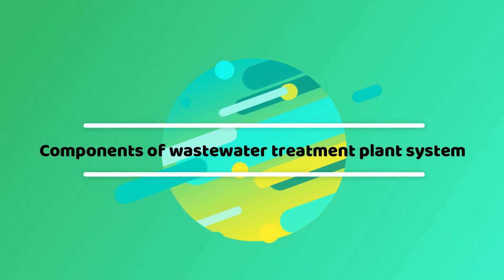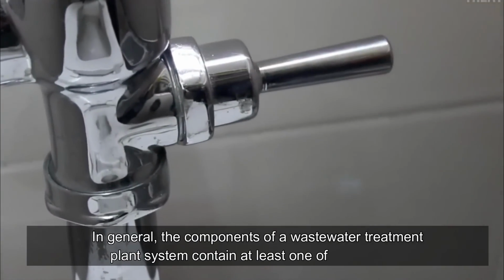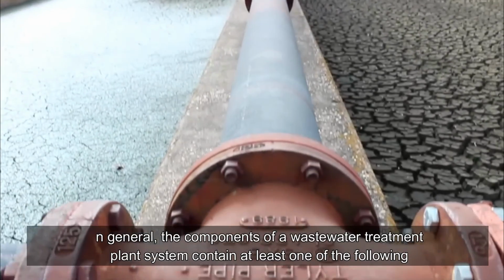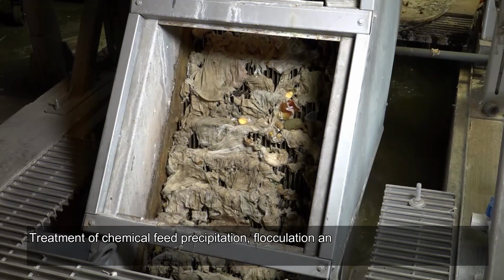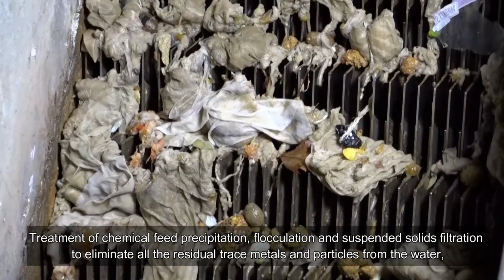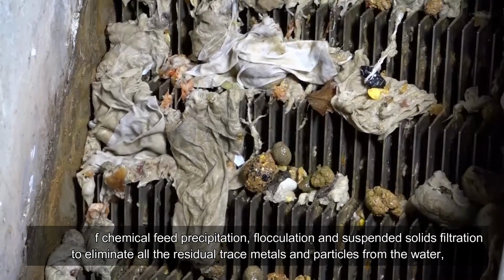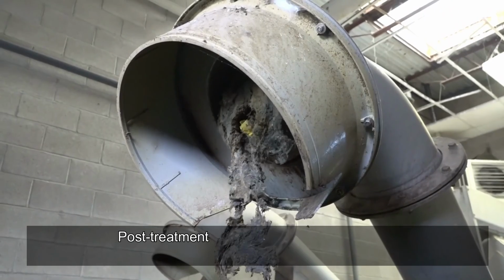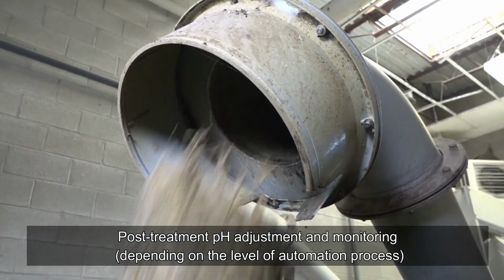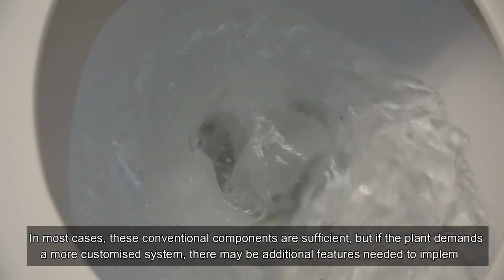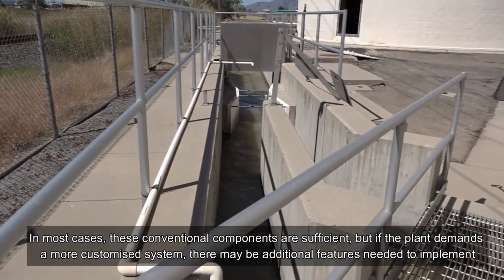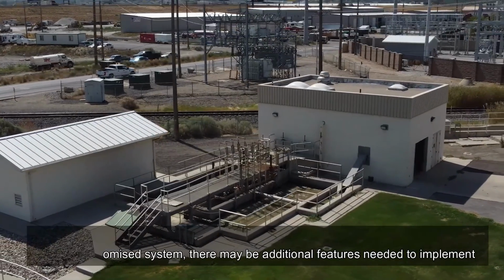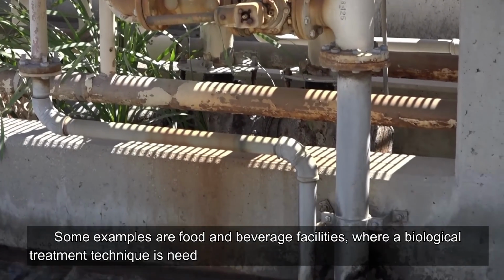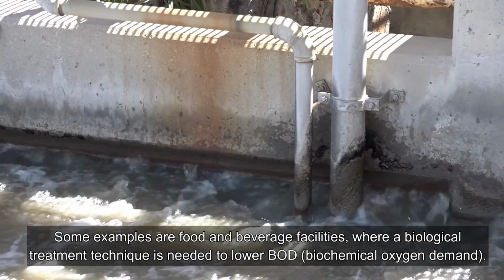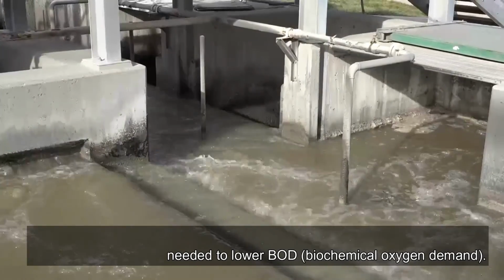Components of wastewater treatment plant system. In general, the components of a wastewater treatment plant system contain at least one of the following: treatment of chemical feed, precipitation, flocculation and suspended solids filtration to eliminate all the residual trace metals and particles from the water. Post-treatment pH adjustment and monitoring, depending on the level of automation process. In most cases, these conventional components are sufficient, but if the plant demands a more customized system, there may be additional features needed to implement. Some examples are food and beverage facilities, where a biological treatment technique is needed to lower BOD, biochemical oxygen demand.